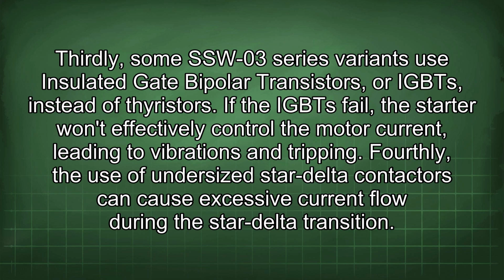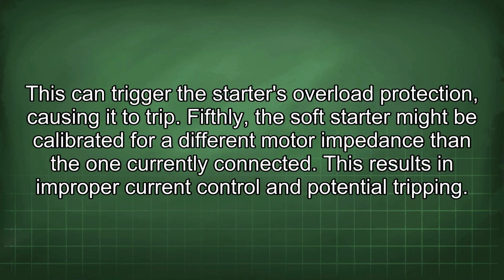Fourthly, the use of undersized star-delta contactors can cause excessive current flow during the star-delta transition. This can trigger the starter's overload protection, causing it to trip. Fifthly, the soft starter might be calibrated for a different motor impedance than the one currently connected. This results in improper current control and potential tripping.